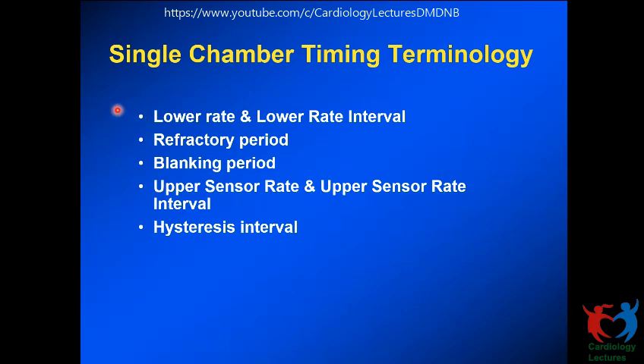So in a single chamber timing, you have a lower rate and, corresponding to that, a lower rate interval, and you program a refractory period and a blanking period. We'll see why they are there. And if it is a rate response pacemaker, you also program an upper sensor rate. We will talk about that. And then there is something called hysteresis, we'll talk about it.